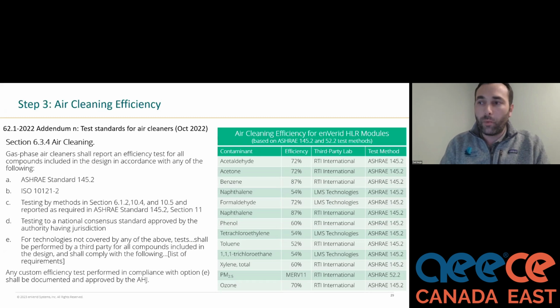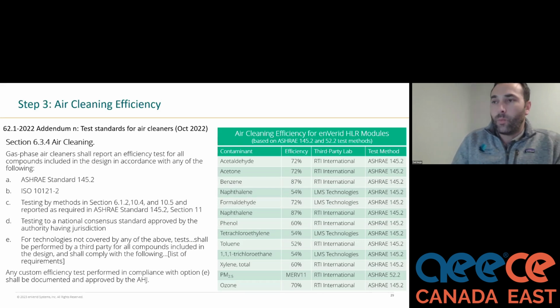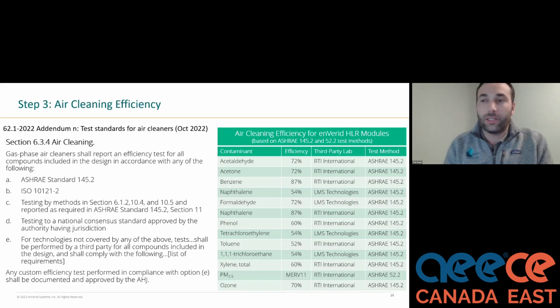There are a few other tests here, but worth mentioning is under section E. They do call out that if a manufacturer believes that their device can't meet one of these other standards, there can be custom tests allowed for each of these contaminants of concern, but the authority having jurisdiction, local code, must specifically approve that custom test in advance. So it's probably worth just using a product that's already tested to something like ISO 10121-2 or standard 145.2. And off to the right there, you can see the third-party lab tested efficiencies for sorbent filters.